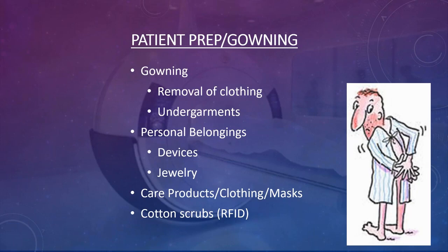People are now wearing athletic clothing such as Lululemon yoga pants and sweat tops that are lined with copper and silver for sweat protection. There has actually been a case where Lululemon pants caught fire in the magnet because the RF energy heated up the metallic fibers.